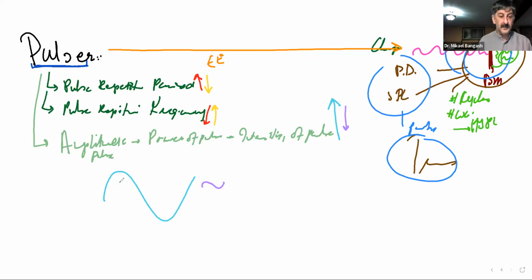Mainly, these are the big waves, or big amplitude waves, or high power waves, or high intensity waves, joined wave after wave after wave to produce a number of waves, which produces a pulse. Or less amplitude waves, wave after wave after wave, joined to produce a pulse. But the number of waves or cycles that make up a pulse was controlled by the transducer, or more correctly by the backing material of the transducer. Did that make sense?